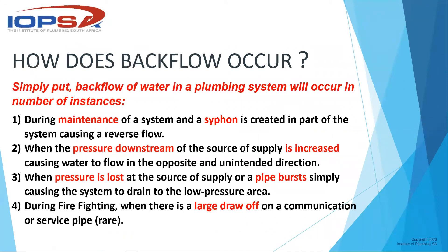How would backflow occur? The municipality is normally pushing water towards us, but water flows to an area of lesser pressure to equalize the system. If the municipality cuts the water supply due to maintenance or a burst pipe, that creates a reduced pressure scenario and water from our installation can flow back. Alternatively, if we increase the water pressure at our installation with a pressure pump, our pressure becomes higher than upstream, and water can flow back in that direction too.